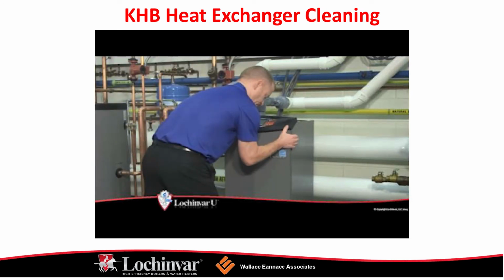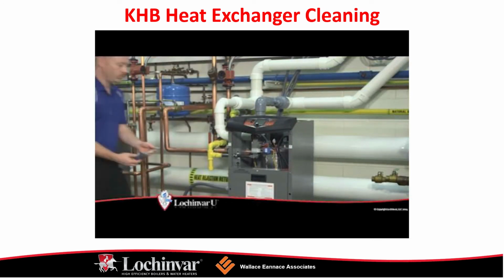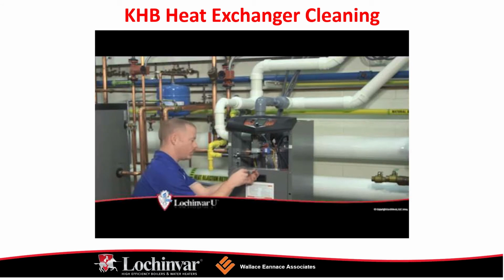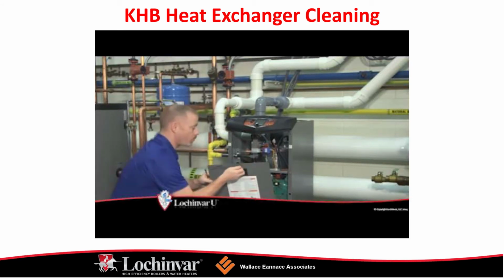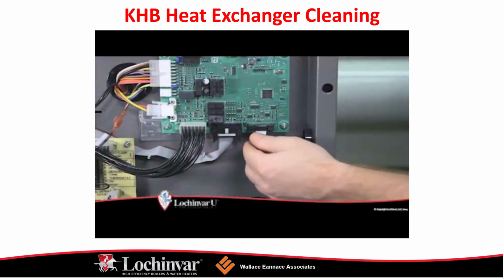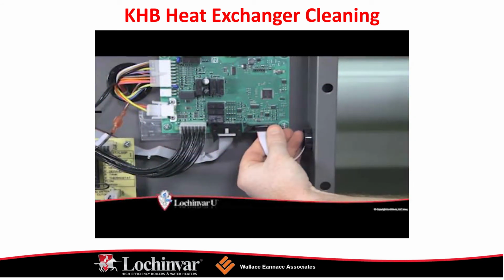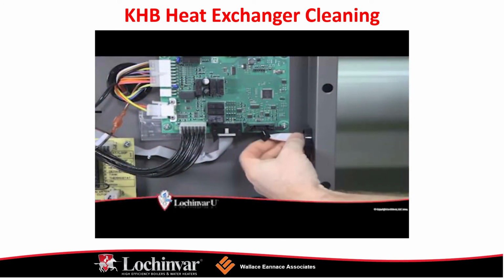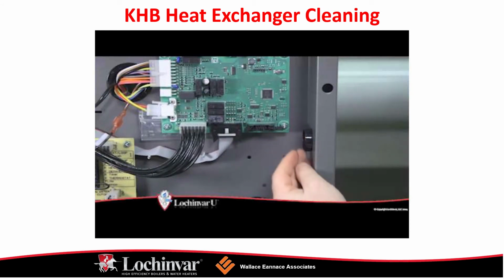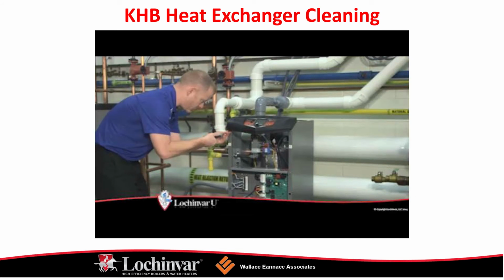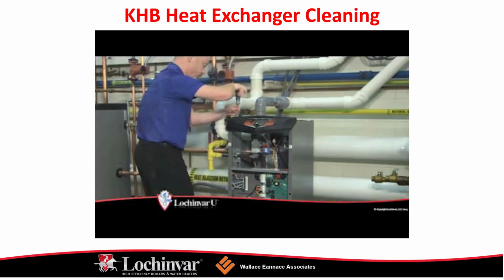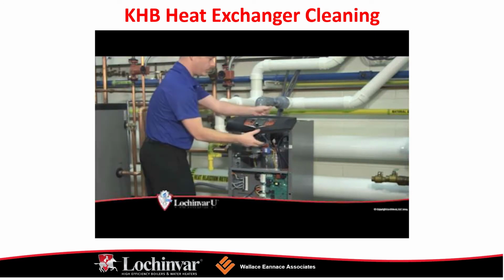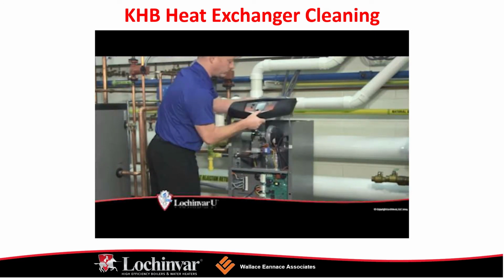Very important. I met a plumber about a month ago who was having some issues. They turned out to be due to improper venting, but when I asked him to please remove and clean the burner, he used an 18-volt Milwaukee leaf blower, and it didn't exactly do the job. So we like to just make sure that you understand that we want to use compressed air. Then we want to clean the blower wheel as well.